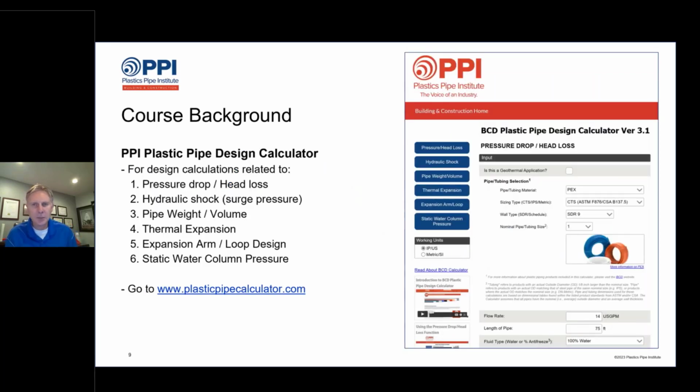Some other information to know about when we talk about designing PEX plumbing systems and sizing pipes. We're going to get into that in more detail in the second part of this presentation next month. But there is an online calculator that is intended to help with sizing pipes properly. We call this the PPI Plastic Pipe Design Calculator, and you simply go to plasticpipecalculator.com. It's a free online app that anybody can use, and it does 6 major types of design calculations, from pressure and head loss to hydraulic shock, pipe weight and volume, and thermal expansion. It'll also help design expansion arms and loops, and even calculate static water column pressure for tall columns of water. This was launched in 2015, and it's a very popular tool. It works for PEX and CPVC and polypropylene and PERT and other plastic pipe materials as well.